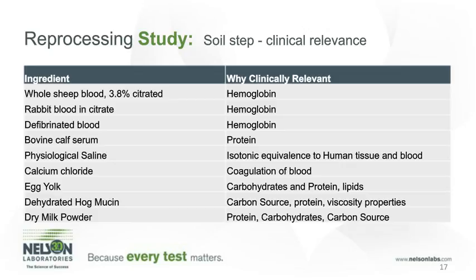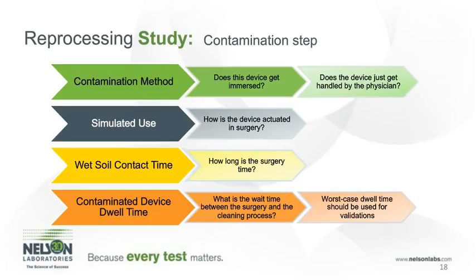Probably the most important part of cleaning validation are the contamination steps. In the contamination, we want to ensure that we are simulating the surgical procedure exactly. So we want to ensure that we are immersing the device, handling the device with bloody gloves like the physician would do, and performing actuation of the device as it would be performed during the surgical procedure. Then we need to ensure that the device is held in the test soil for the amount of time that the surgery would take. The final part of this is to ensure that the soil is dried onto the device, as we need to simulate the time that it would take for the device to move from the OR suite to the central processing area to be cleaned.